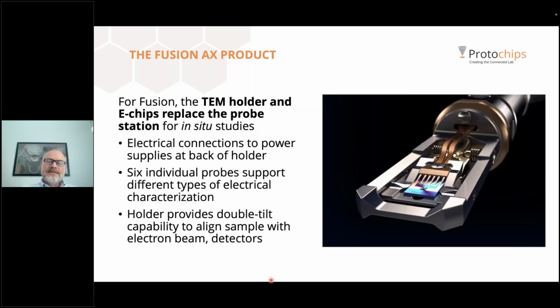Now, the part of the system that I think is most different from standard characterization is the combination of holders and chips. The TEM holder and chips replaces the probe station for in situ studies. Probe stations are usually large benchtop units that don't have to worry about space, but to fit in the TEM, we have to miniaturize the whole thing to fit into a pole piece gap less than 2 millimeters thick. Now, most of you are probably familiar with a holder, like shown here. For fusion, we have connections to electrical cabling at the back of the holder. That's the part that sits outside the microscope.